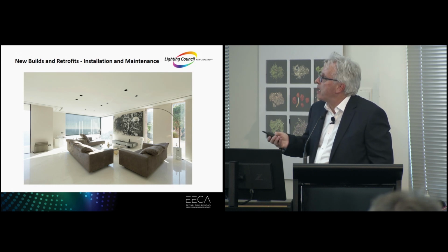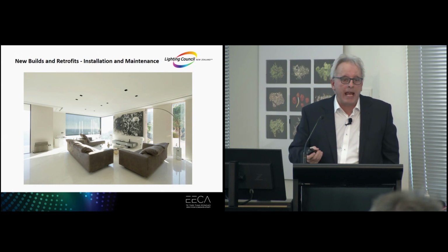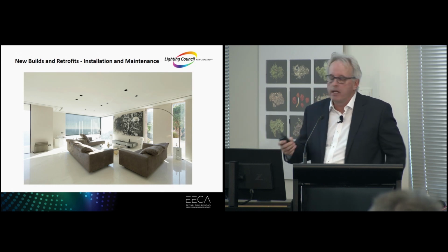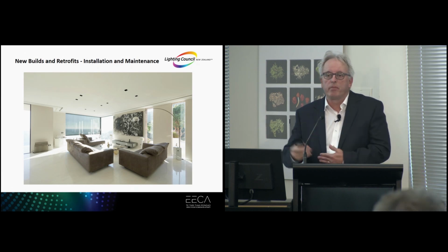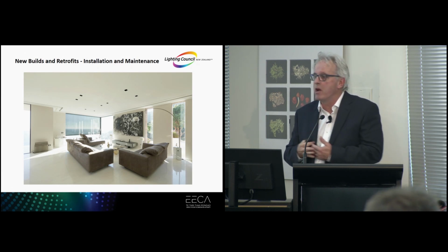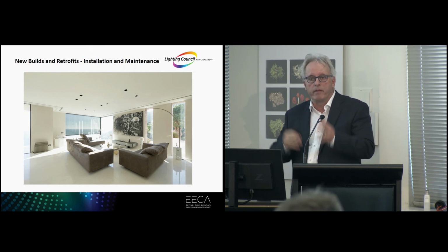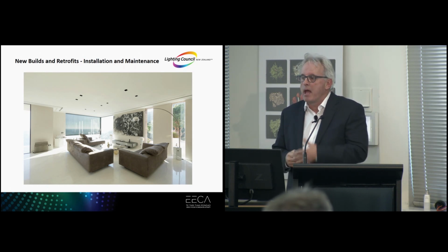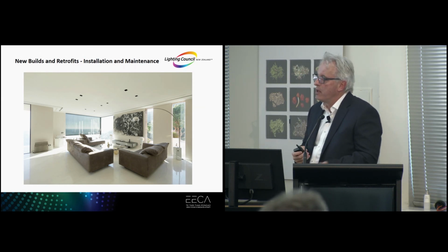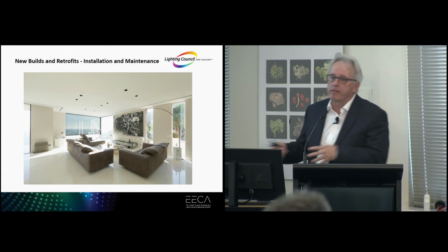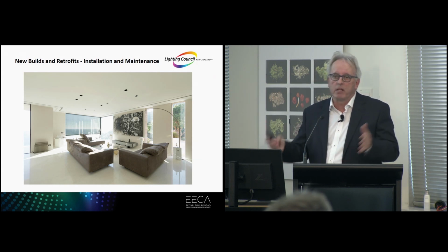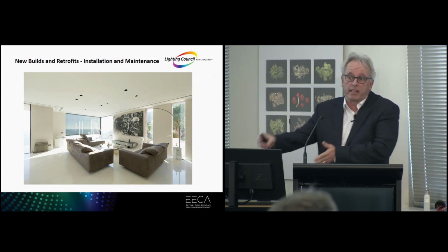Brian spoke briefly about the idea of just changing the lamps. That again is a tricky thing. Just changing the lamps does provide the savings today, although nowhere near, you're probably only going to pick up half the energy saving that you would if you changed the fitting. And the other thing is, of course, it's not locking it in. So if you change all your lamps to an LED lamp, it's a marvellous thing. We've perhaps saved half our power. We could have saved 80 or 90%.